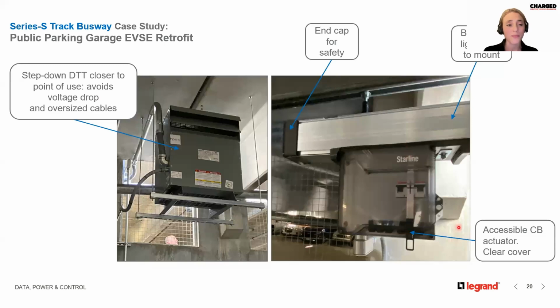So here's a close-up of our IP54 Series S, one of the plugs, and you can see the breaker inside. It has an actuator, so you can pull it from the outside without opening the lid. Contractors love this because the breaker isn't in the panel board but at the exact point of use, and they can turn it on and off as needed for safety while working. They don't have to go all the way back 82 meters to do that. The end cap is for safety.